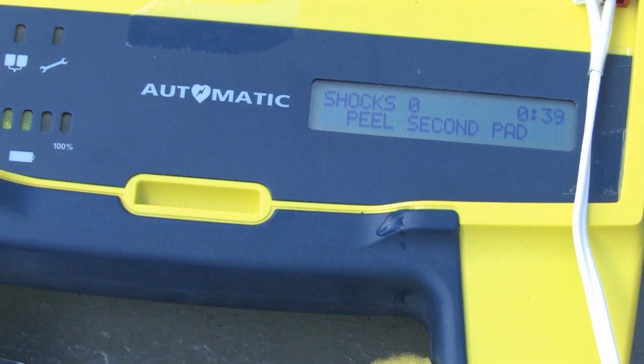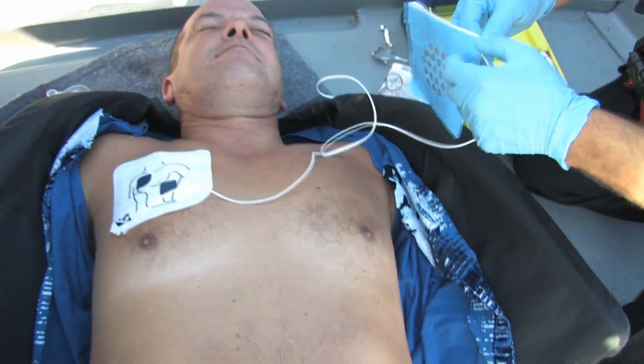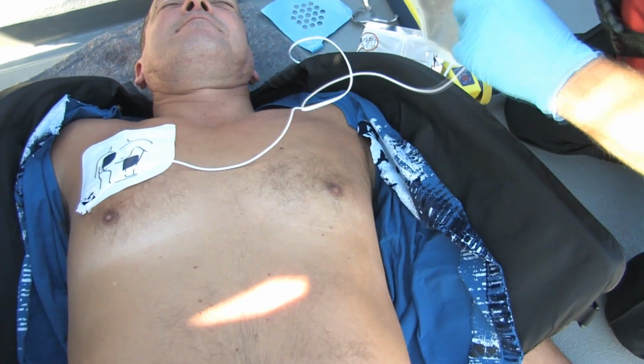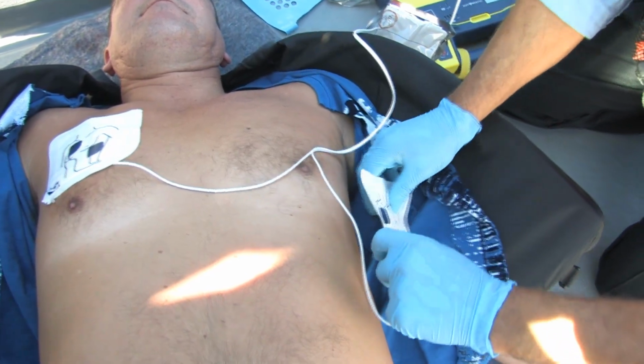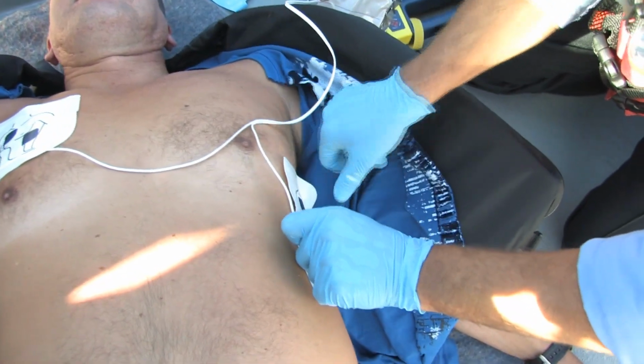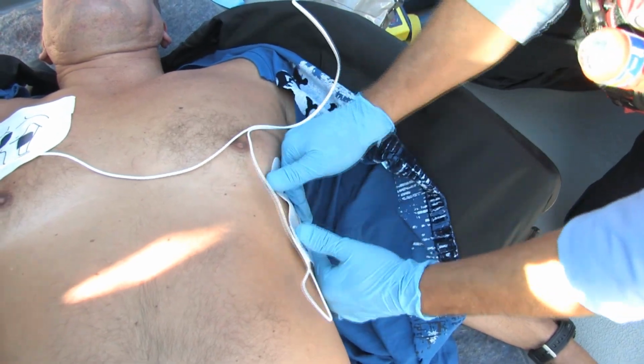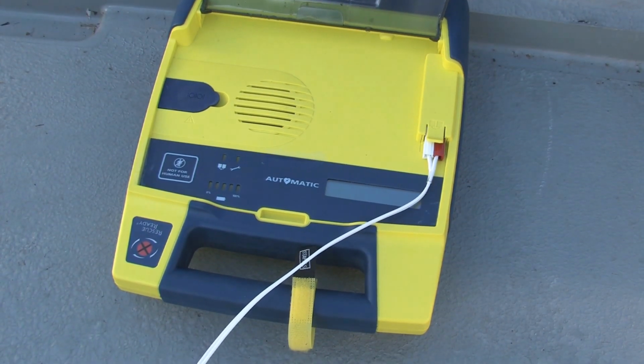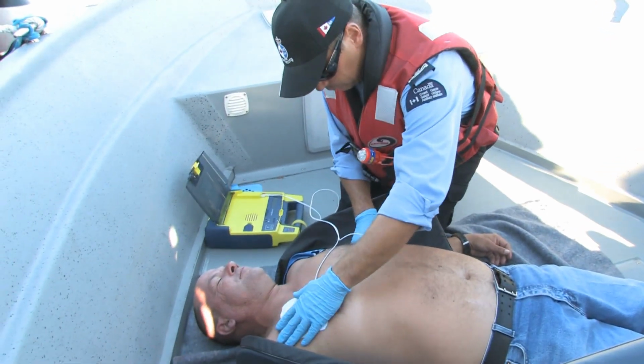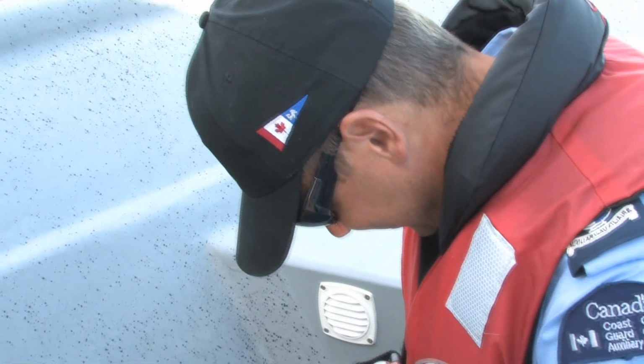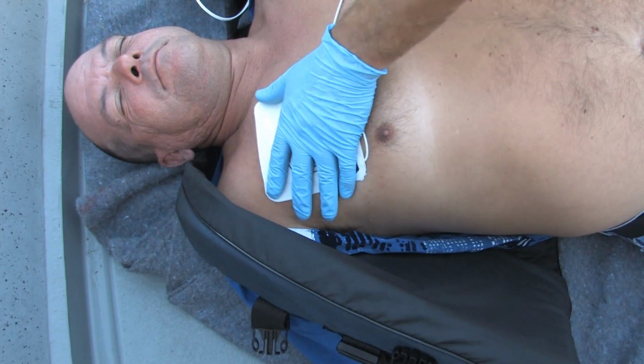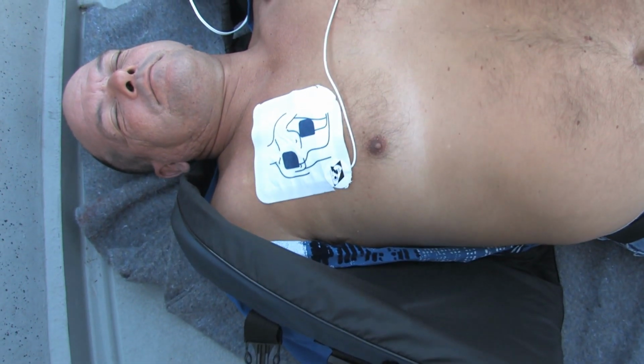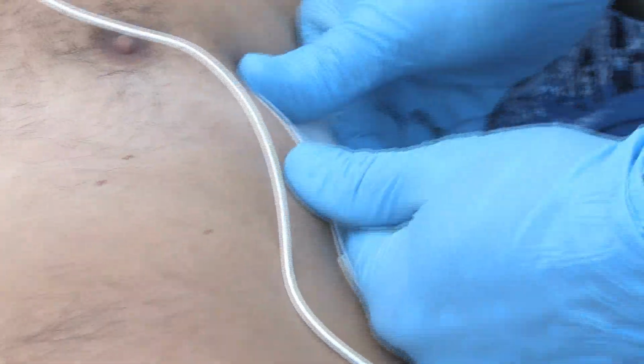Peel second pad and place on bare lower chest as shown. Peel away the second electrode and place it on the left side of the bare lower chest, also face down as per the diagram. If you hear this prompt, check pads, check pads, it means the electrode is not making sufficient contact. Press down to make sure the electrodes are firmly attached to the victim. If this error message repeats after you've pressed down on the pads, remove these electrodes and replace them with new ones.